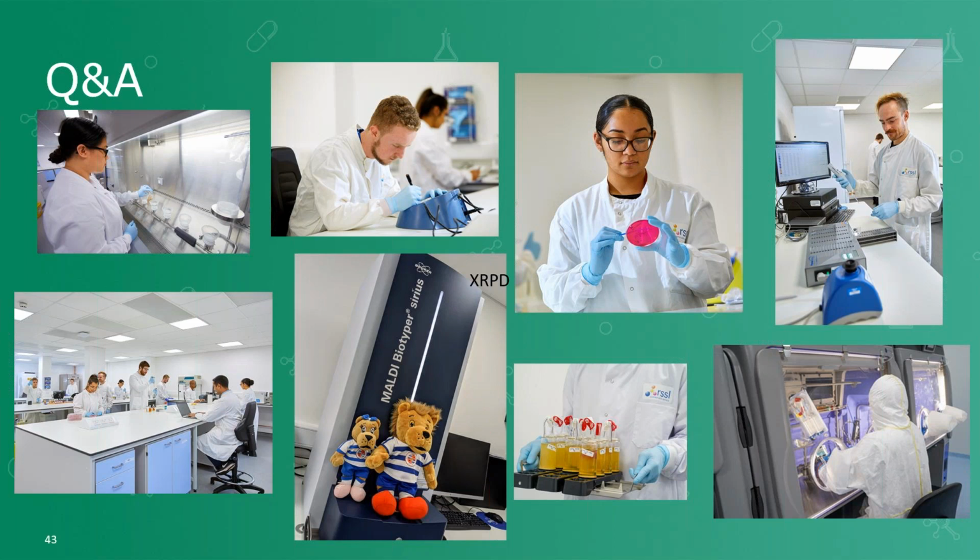So I've got a question from somebody, Jane, who said, how can endotoxin enter a water system? The one experience I had with endotoxin in a water system was a repair where a valve needed replacing.